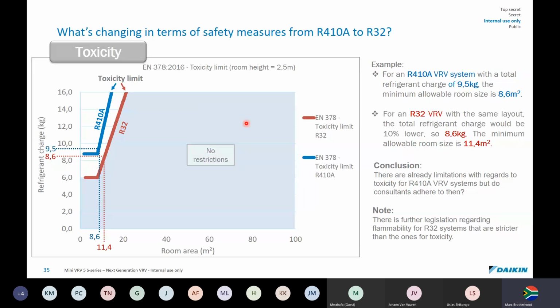If we add these two together on a system, so for a typical VRV system with a total refrigerant charge of say 9.5 kilograms, the minimum allowable room size will be 8.6 meters squared. However, if we use an R32 system with the same layout, the total refrigerant charge will be 10% lower. So if we take 9.5 kilograms, we know that the R32 system uses 10% less gas. You take 0.95 of that, you subtract it, and you'll get 8.6 kilograms. Now the room size can go up to 11.4 meters squared.